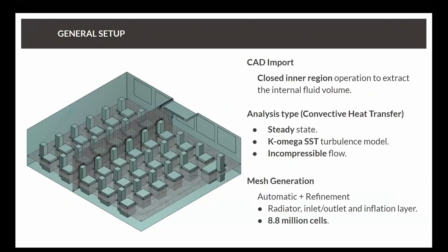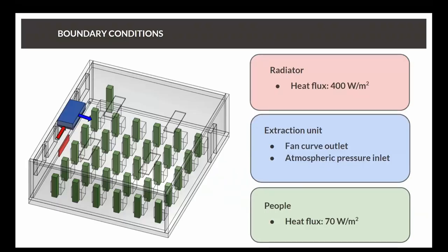Jumping to a general setup. First, once we import the model in the platform, I will show you later on in the live demo. But we need to do a closed inner region operation to get this model we can see here in the picture. It is mainly just extracting the inner volume where the fluid will be simulated inside the room as we are not interested in anything else. Once we have this, we choose the analysis type. In this case, the convective heat transfer with a steady state and SST turbulence model incompressible flow. Then the next step is to generate this mesh. I have to say that it's automatically generated like we have defined some inflation layer refinements, some refinements in the people, in the radiator. But it is really straightforward and automatic.